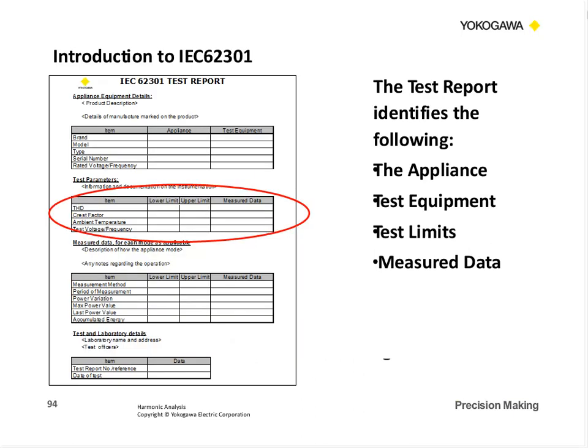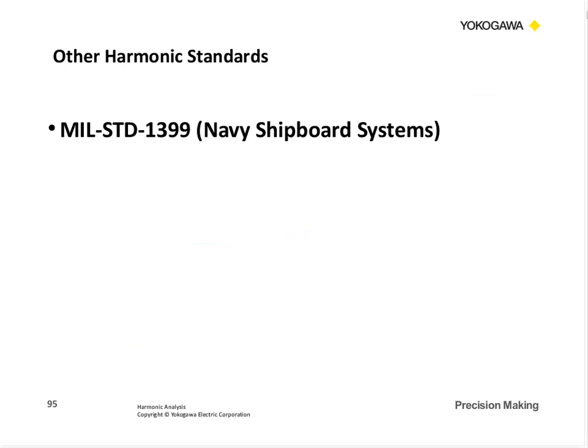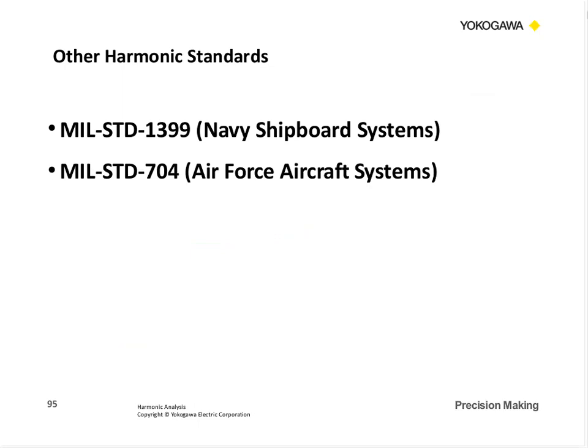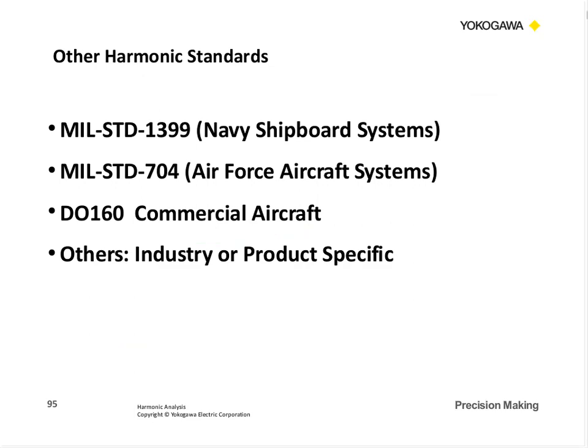And so there's a test report that can be generated from our test software, and you identify the appliance, the test equipment used, limits, measured data, all that's in the test report. And it does require the harmonics testing. A lot of other harmonic standards, such as Navy has a MIL standard, 1399, Air Force is a 704. The DO 160 for commercial aircraft, they have theirs, and there's other that we see as industry or product specific harmonic standards. So generally, the instrumentation will deal with most of these measurements.